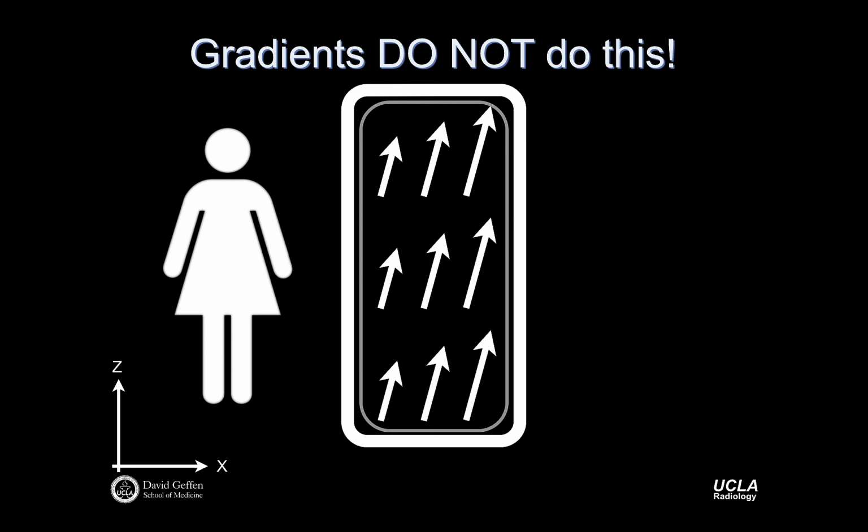Okay, so that's for the most part a qualitative treatment of how the gradient system is put together and what its effect is. We'll talk a little bit about the mathematics of it, and then I think we might do this for a bit and then take a break. So at least one more chunk of slides here. The mathematics for this can be a little clumsy, but we're going to drop most of it pretty quickly. So you basically heard me say it already, but gradients are a special kind of inhomogeneous field whose Z component varies linearly along a specific direction that we call the gradient direction.